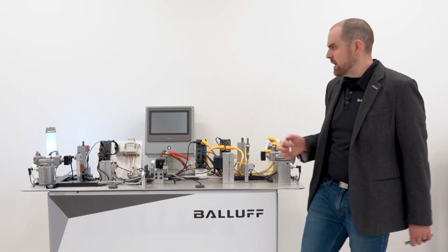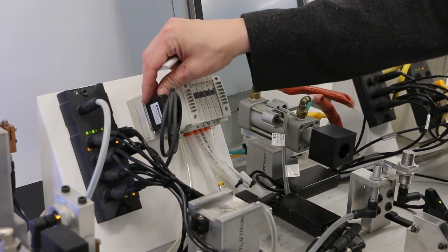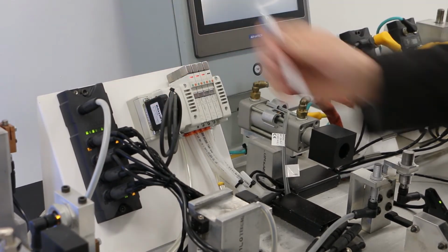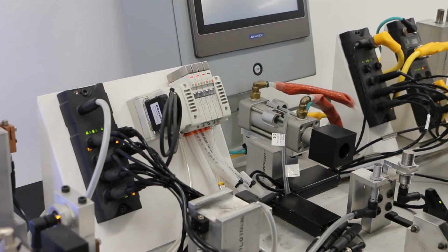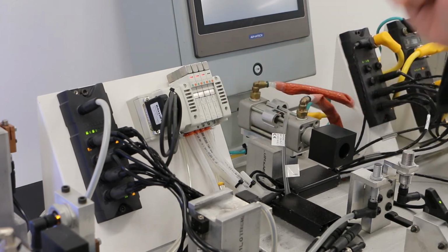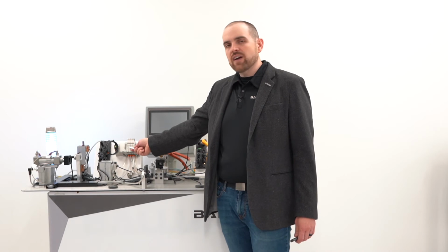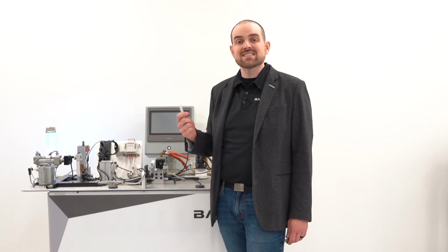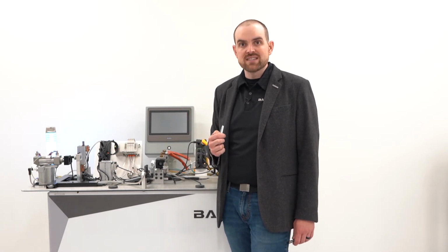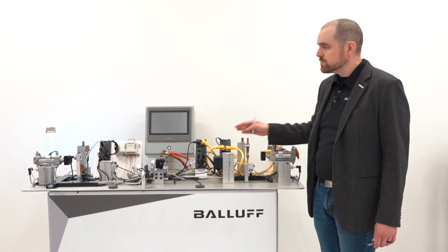But other options are out there. This here is a valve manifold. The valve manifold is a standard D-sub valve manifold that controls all of our clamping cylinders. But this valve manifold connector actually allows us to connect back to the master and control the complete valve manifold over that connector. Also, many of the valve manufacturers make an IO-Link valve manifold. So then what you get if you have an IO-Link valve manifold is all kinds of diagnostics and information from the valve manifold itself, and that information can be reported back through the IO-Link master.